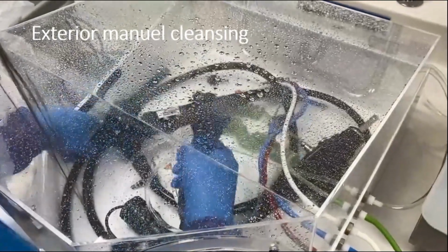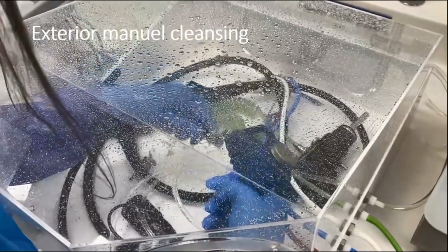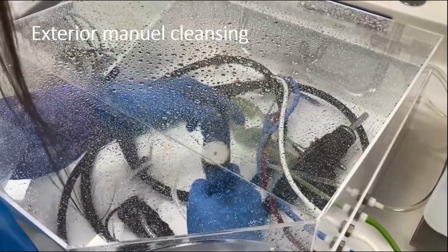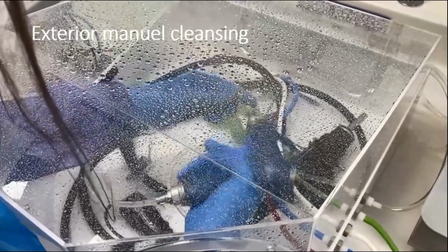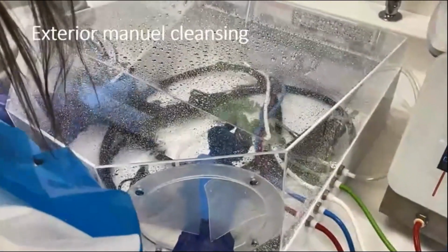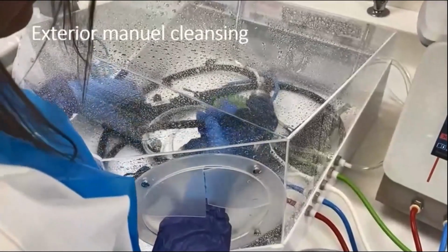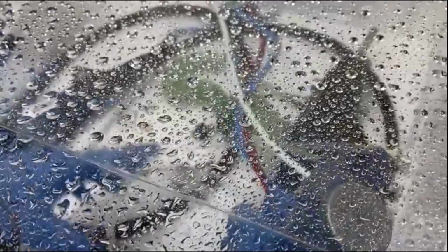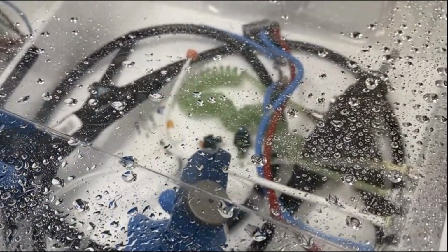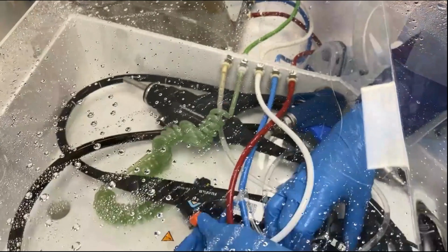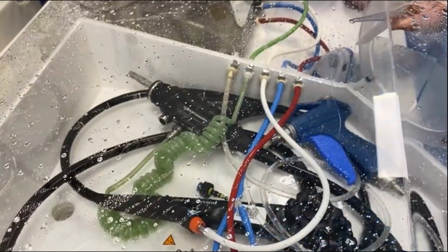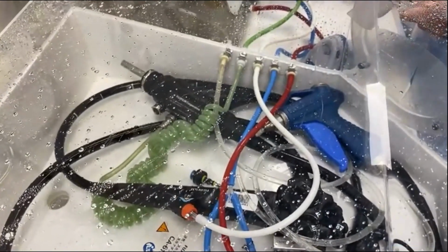The next step is an exterior manual cleansing with a water jet. As it is a duodenoscope, you have to clean under and above the elevator. So you have to move the elevator and clean again. And the automatic step starts now. To check all the connections, you have to put the last connector on the operative channel. So the operative channel is connected, and we start the automatic cycle.